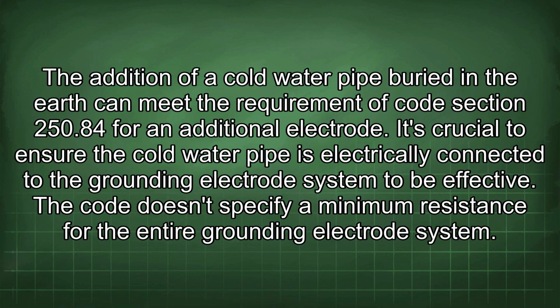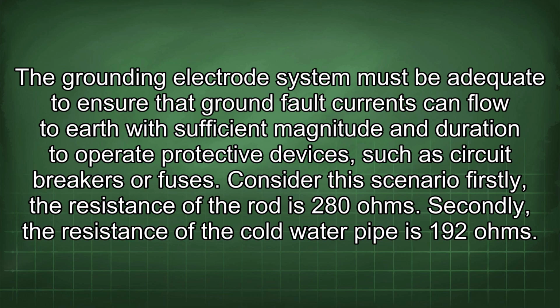The addition of a cold water pipe buried in the earth can meet the requirement of code section 250.84 for an additional electrode. It's crucial to ensure the cold water pipe is electrically connected to the grounding electrode system to be effective. The code doesn't specify a minimum resistance for the entire grounding electrode system. The grounding electrode system must be adequate to ensure that ground fault currents can flow to earth with sufficient magnitude and duration to operate protective devices, such as circuit breakers or fuses.